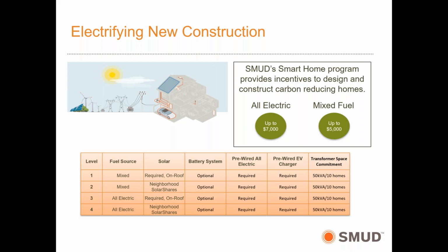When we look at EV charging, we mainly think about 1.2 kW for level 1 charging or 6.6 kW for level 2 charging. However, newer generations of EVs support much higher charging rates—for example, Tesla has a charging option at the residential scale as high as 19 kW. Considering that EVs are normally about 1/2 to 1/3 of a residential home's load, that level of EV load creates significant risk of infrastructure overloading and could result in increased grid infrastructure costs. By including full pre-wiring of the EVSE in the home design at 6.6 kW, we're lowering the bar to EV adoption and home charging, but not encouraging the use of very high-powered EVSEs for residential applications. Customers can upscale if they need to, but at least this gives the baseline for customers to just plug and play.